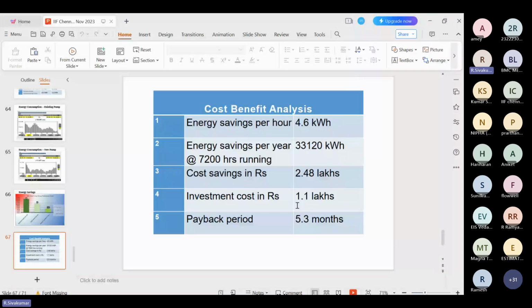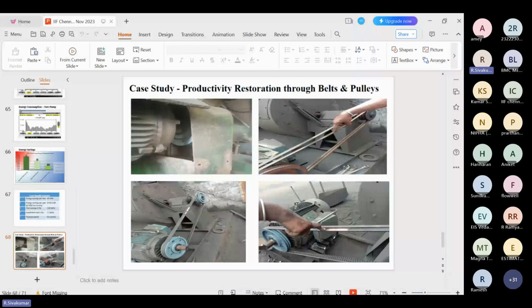So again, this is one example: productivity restoration through the belt and the pulley. Normally belts and pulleys are a very, very ignored area in any industry, but some savings can be achieved through this. See, this is one of the dust collection systems used in the sand plant, the shot blast dust collection system. This blower capacity is 20 HP. Okay, the blower motor capacity is 20 HP.